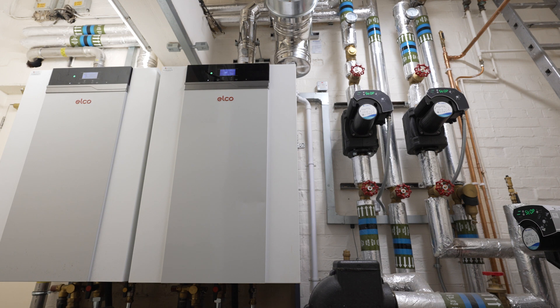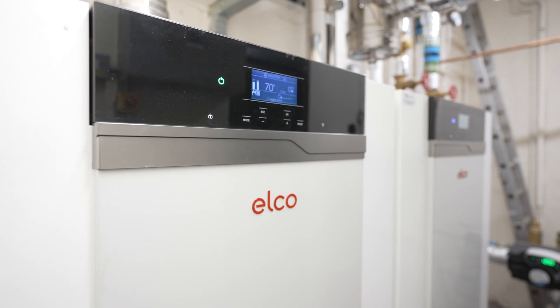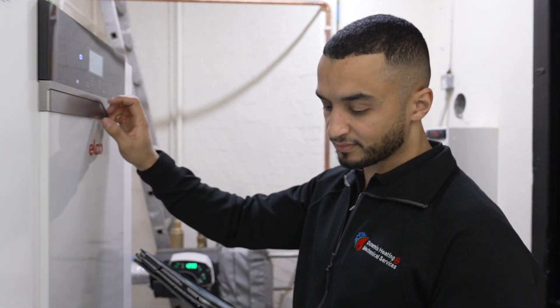My name is Mark Ferris. I'm Specification Manager for Elco Heating Solutions. The Thision range is suitable for tight plant rooms like this. The modular arrangement is such that the boilers only need about 10 millimetres between them. A 200 kilowatt boiler, or 197, is less than 700 millimetres wide, and when that unit is used in a multiple configuration with eight boilers — up to 1.6 megawatts — it only needs a footprint of just under 3.9 metres by 1.4 metres.